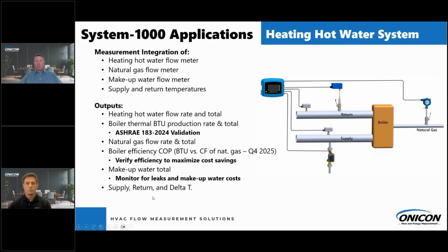This is going to be a natural gas-fired system. So you'll have a heating hot water flow meter. You'll have an ONICON natural gas flow meter that you can see on the right side of the diagram. Again, we have a makeup water flow meter and our two temperature sensors. Now your outputs out of the System 1000, again, are going to be heating hot water flow rate and total. Then you'll have your boiler thermal BTU production as a rate and total. Again, this will help you with your ASHRAE 183 validation. With that ONICON natural gas meter, you'll have your natural gas flow rate and total.